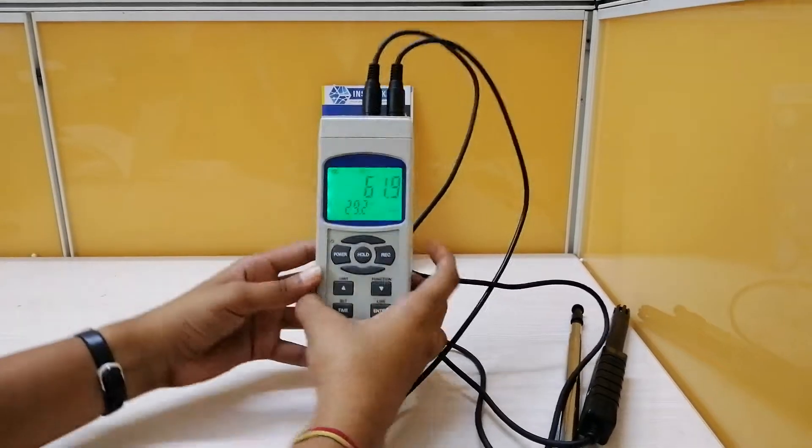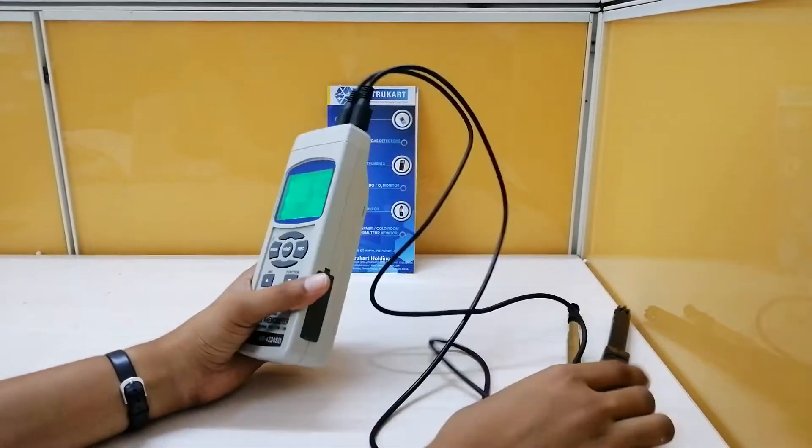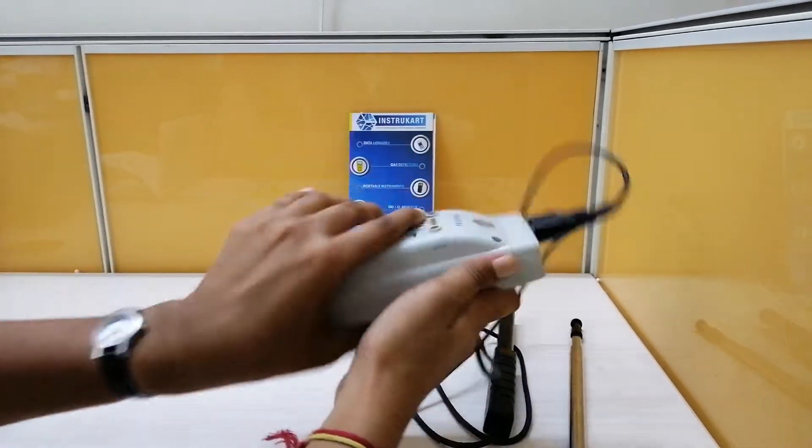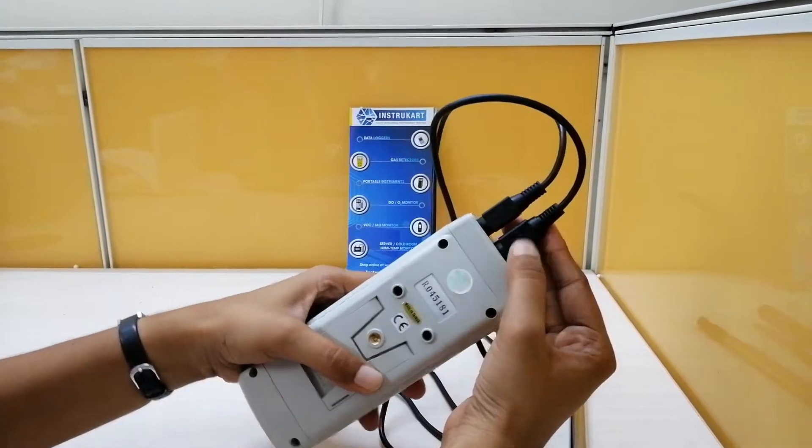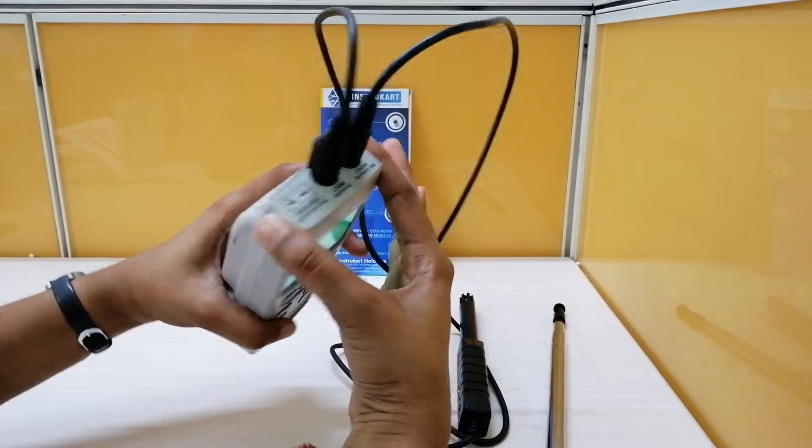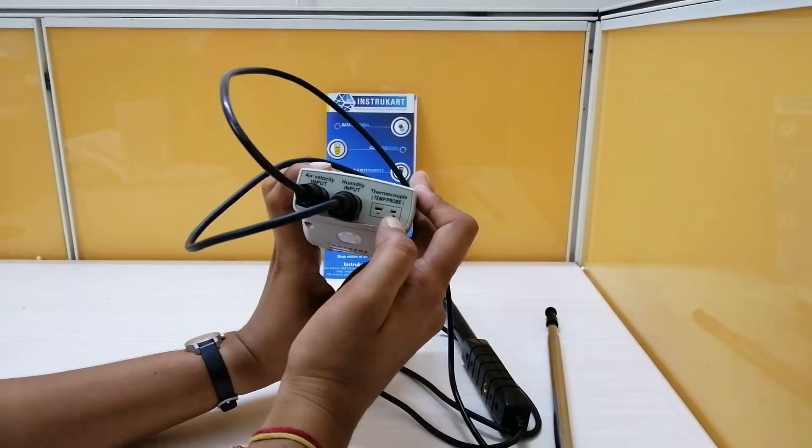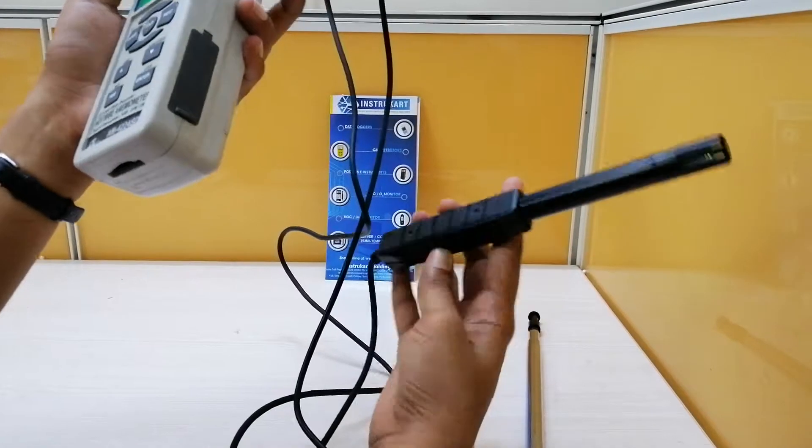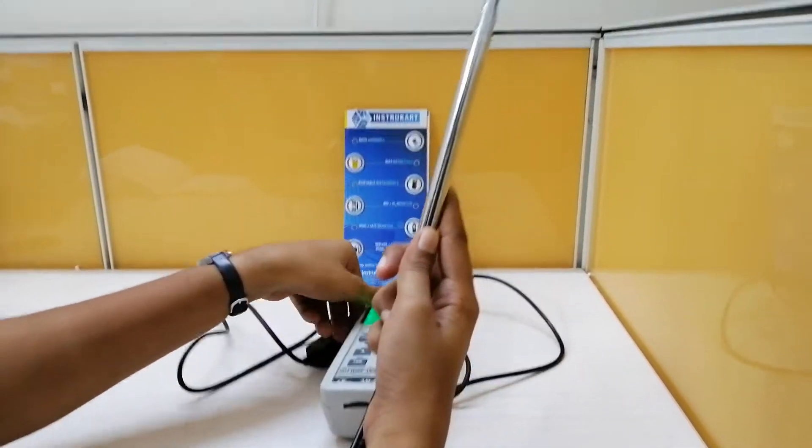You can see here, these are the keys as I was told, and these are the probes. You can see here there is an arrow indication. In the same way you have to put these probes. And these are the provisions for thermocouples as I was told. There is a provision for J type and K type thermocouple. This is the probe for humidity and temperature, and this is a probe to measure the airflow.